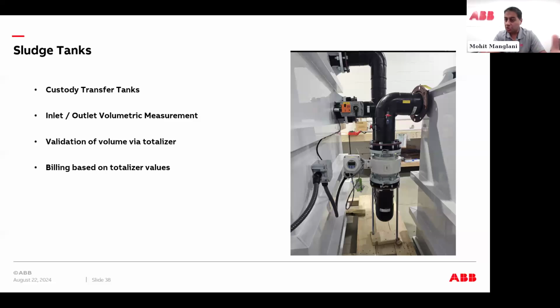Sludge tanks. Again, I'm covering the municipal side. Custody transfer tanks, tanks coming in, tanks coming out. Mag meters, all of them have totalizers built into them for the most part. So if you want to make sure you know what's going into a vessel or a tank or through a station, you have a totalizer built onto the device.